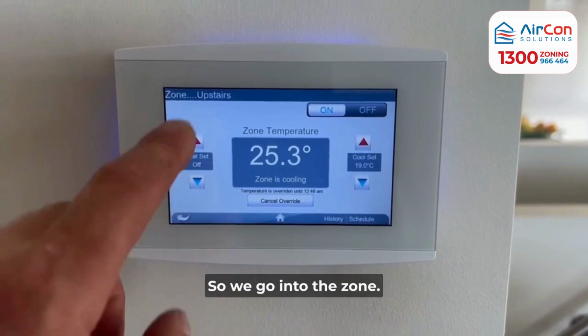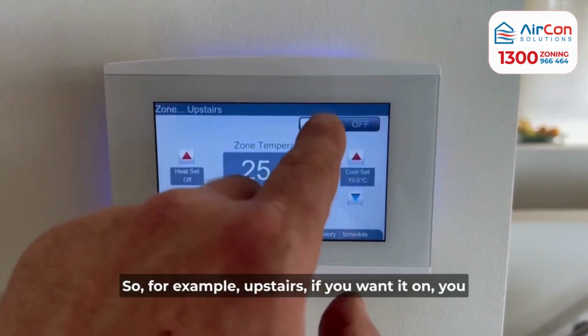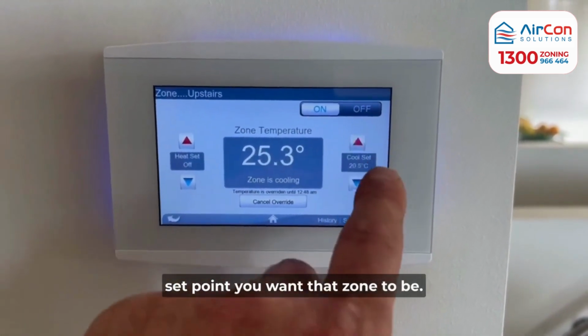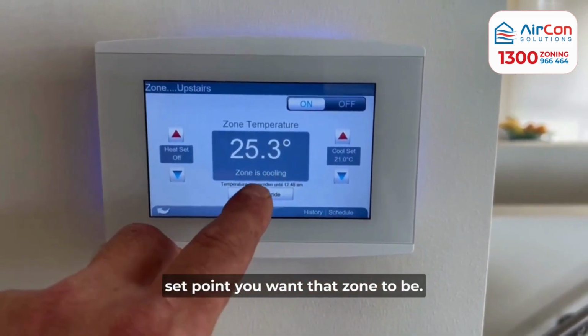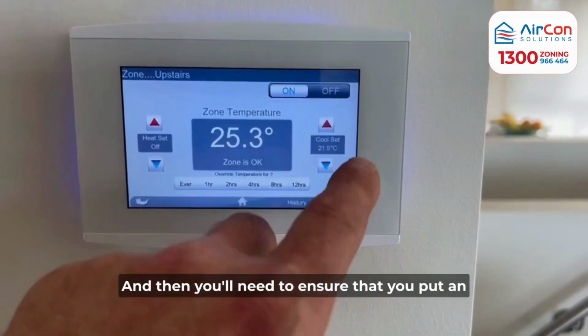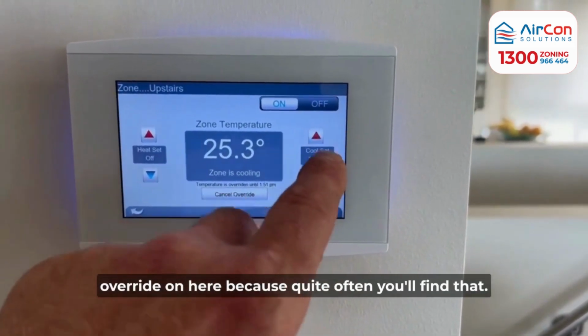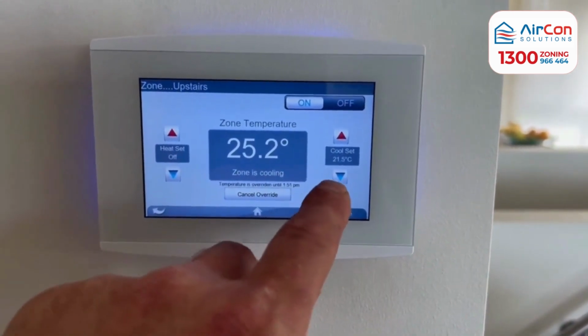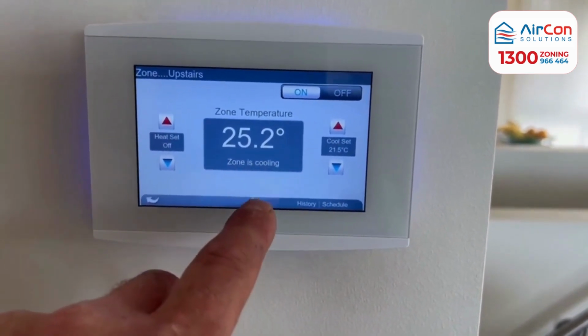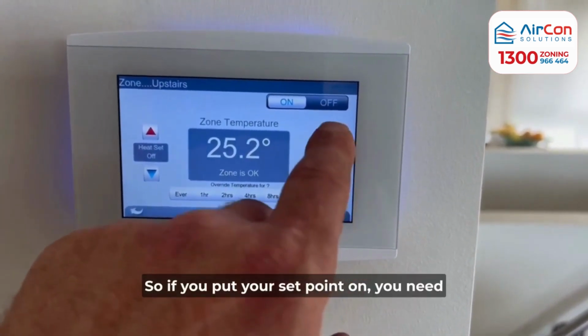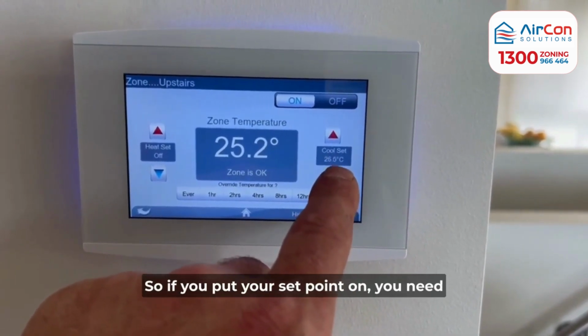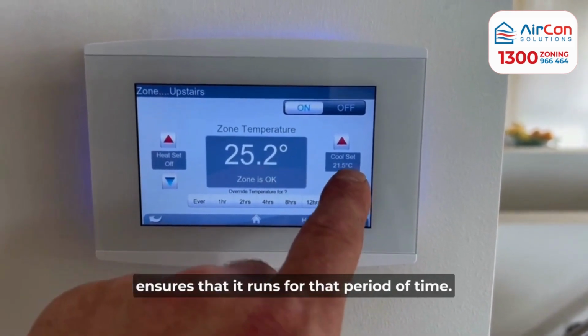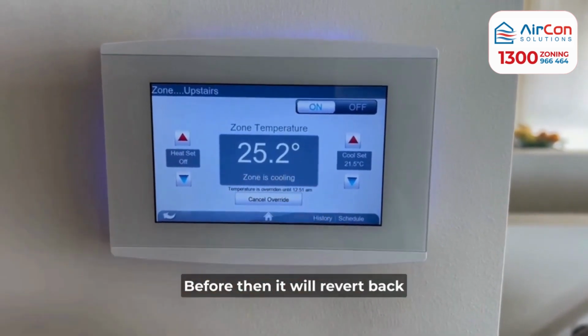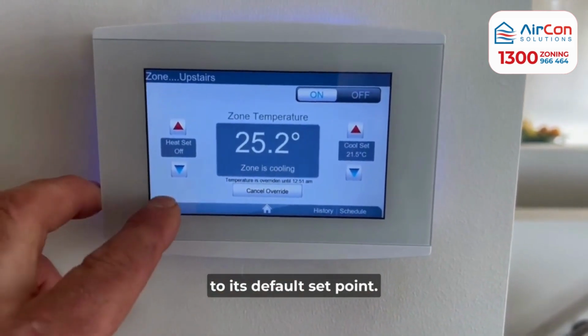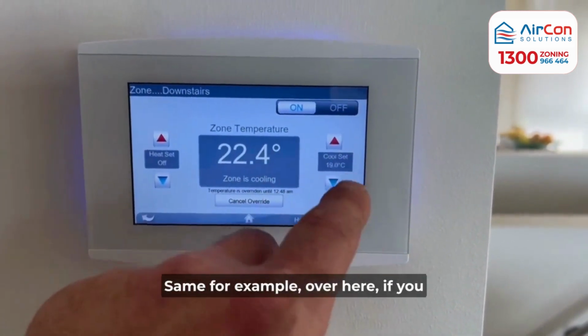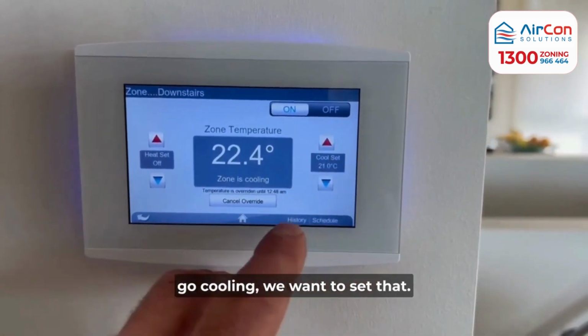So we go into the zone. So for example, upstairs, if you want it on, you tap it to on, and then you dial in the temperature set point you want that zone to be, and then you'll need to ensure that you put an override on here, because quite often you'll find that it will revert. So if you put your set point on, then you need to put an override setting onto it so that it ensures that it runs for that period of time before then it will revert back to its default set point. So for example, over here, we go cooling, we're going to set that.